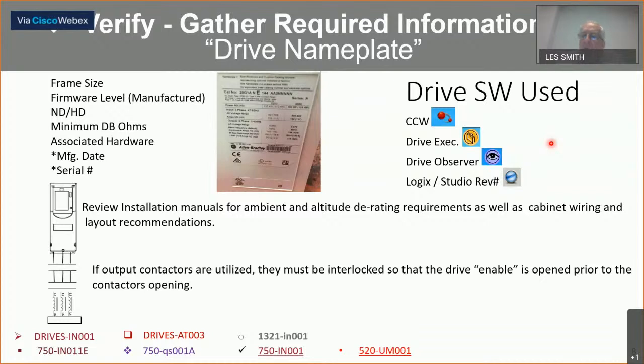Drive Observer is a trending software. I like to run trends so that I can come back and look at what the amperage was, what the voltage was, what the speed was relative to the process, and have a picture of it so that I can better understand it and or pass it along to the customer so they can understand. And then at the bottom, you've got your Logix or Studio software, which will also be able to troubleshoot the drive for you.